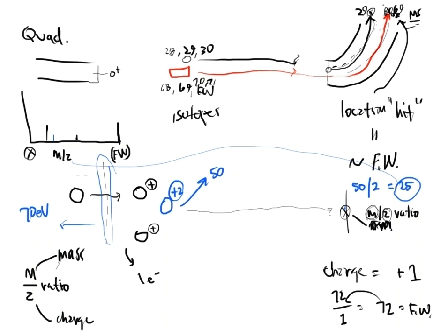Because that's really not formula weight on the bottom. It's really a mass to charge ratio on the bottom. That is where it starts to conflict everything. So, another reason for 70 is to control the positive ones that come from the electron chamber. We want those to be positive ones. We do not want positive 2s involved, because that begins to change our whole concept of what this x-axis really means.